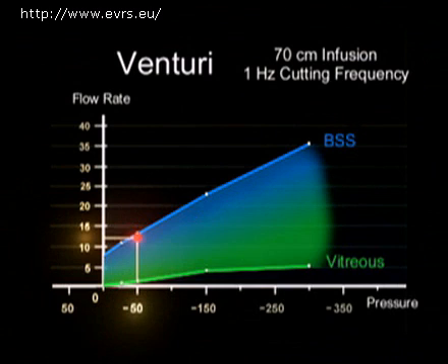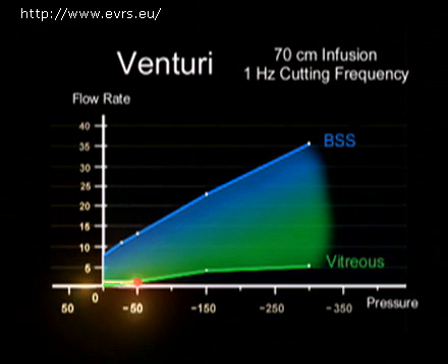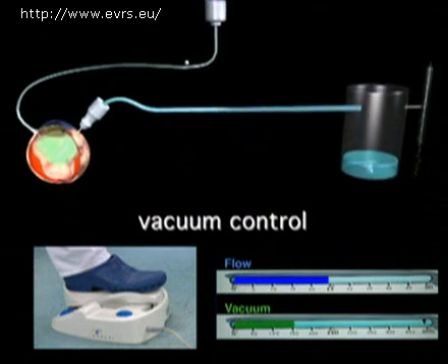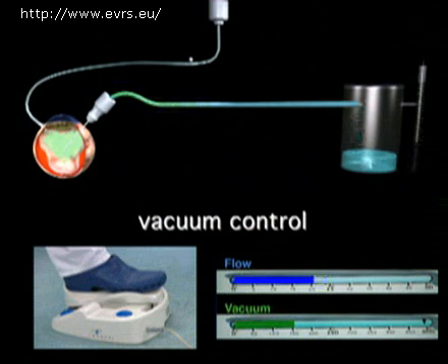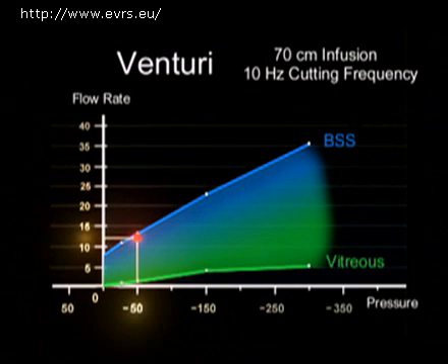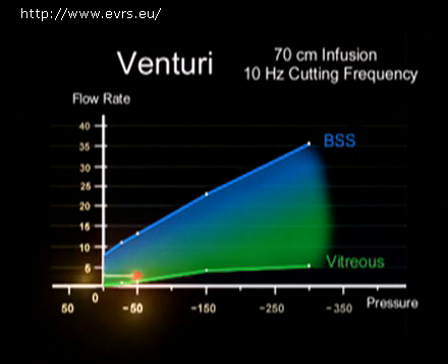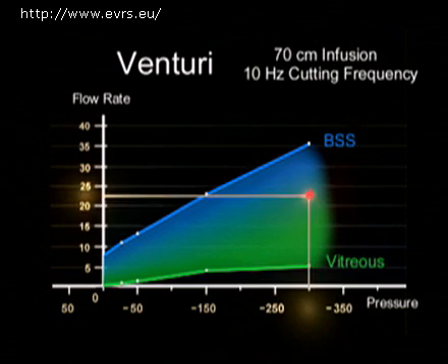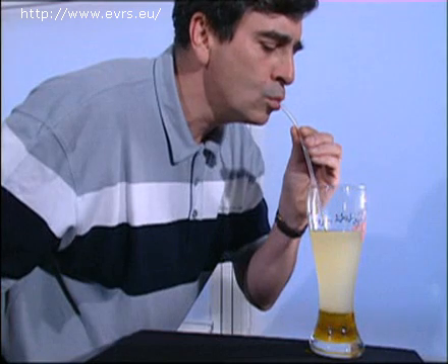Let's now consider the practical consequences in the context of a central vitrectomy. If a venturi pump is used, and if the operator chooses a maximum depression of minus 50 mmHg, the aspiration flow will decrease from 13 cc per minute to 0.85 cc per minute — it would be necessary to spend about half an hour performing the procedure. If the operator is impatient, he or she may use a higher maximum amount of depression, only stepping lightly on the foot pedal at the start and using more force when the flow is too little. The problem then is when returning to BSS, the magnitude of the depression will generate an aspiration flow twice as great as the infusion flow.